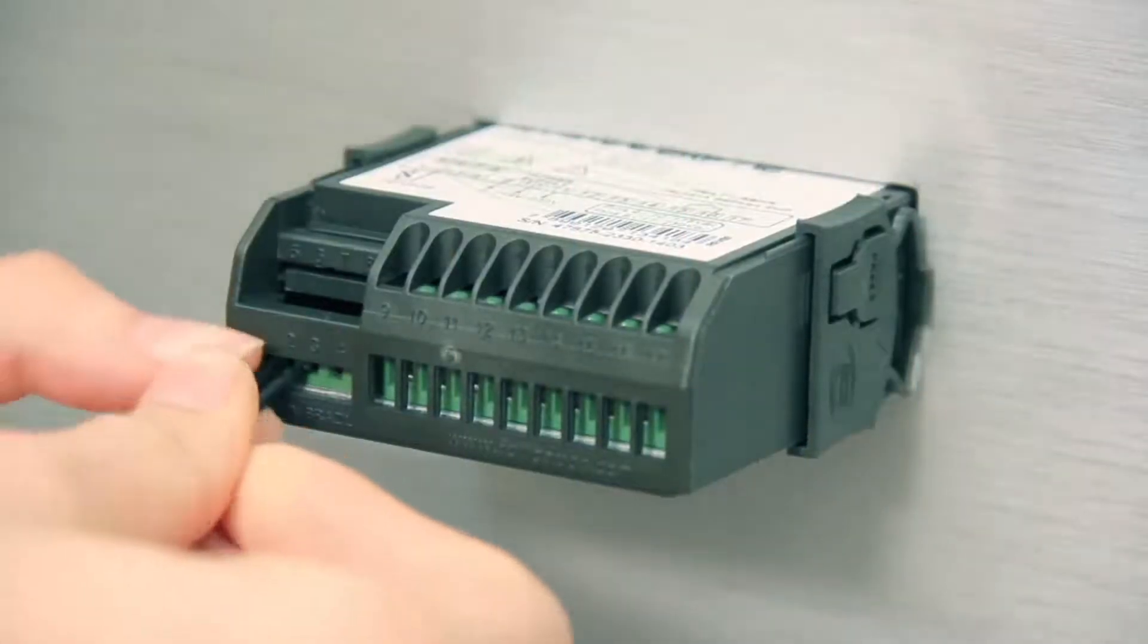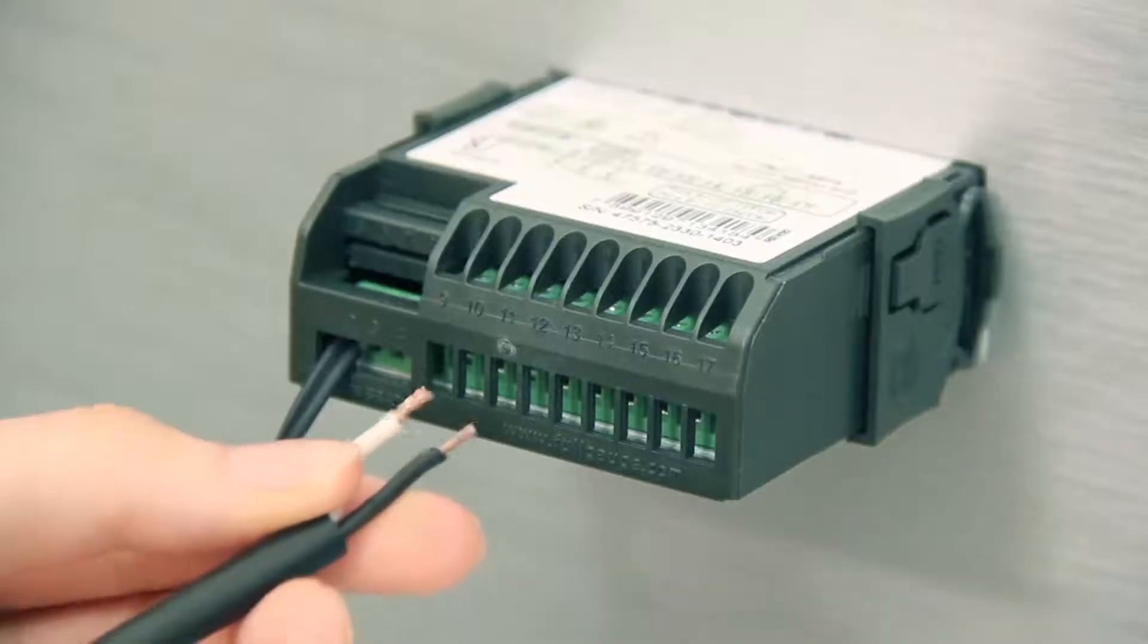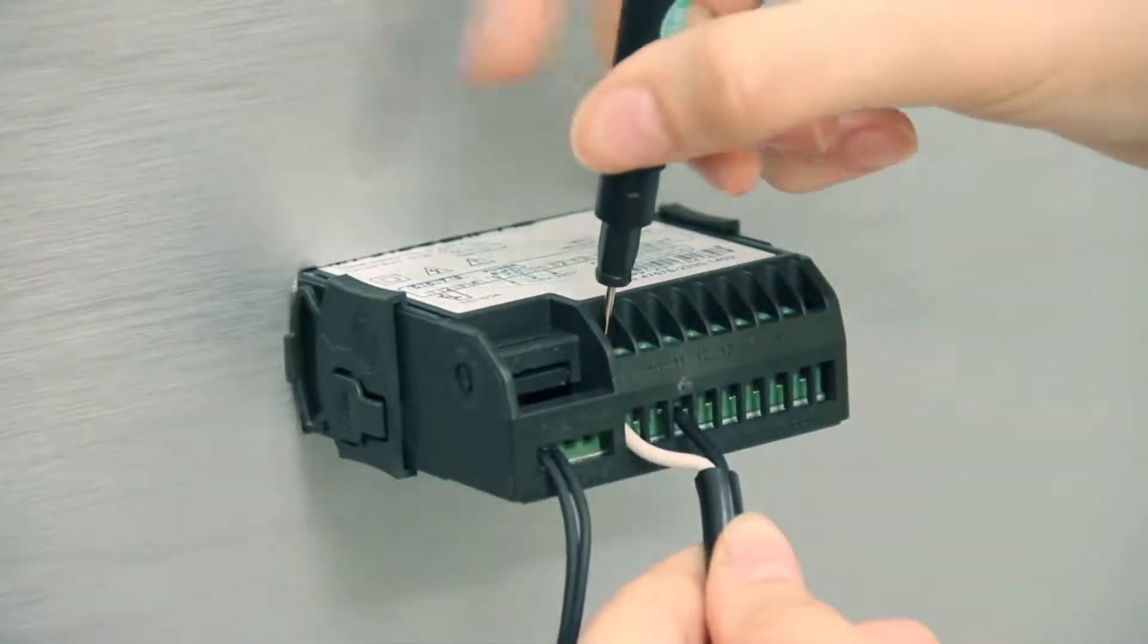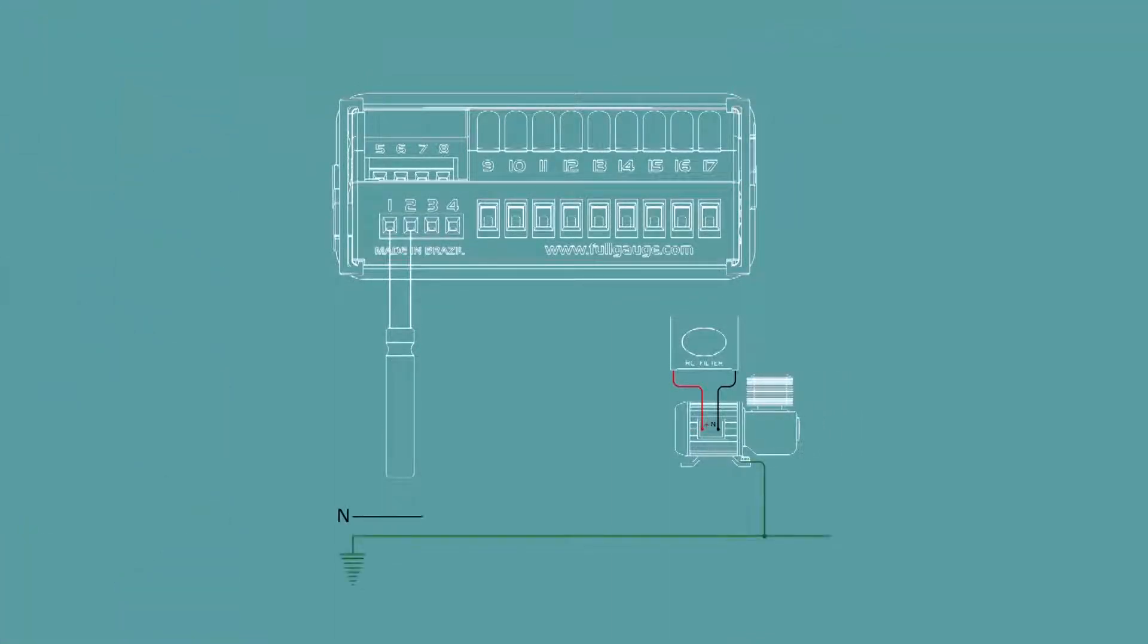We now present two installation examples of the MT512E 2HP. You must configure and install the instrument according to your needs. Cooling installation: Assuming power is less than 2 horsepower, a contact switch is not used. However, the RC filter is used. In this installation example, the supply is made with 127 volts AC.